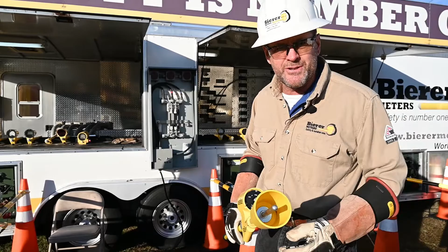You guys see those numbers? They're not making any movement, and that's what you want. It's important you use direct contact tools. A lot of utilities give their guys non-contact tools, and let's say we have an underbuild. The linemen are going to be presumptuous, guessing whether there's induction on that underbuild or not. You really don't know. We got non-contact tools out here two feet away from 19.9, 34.5, and we're getting 69,000 volts. Which line's hot, which line's not? What's the induction? Is there backfeed? You just don't know. So you want to have direct contact tools, always.